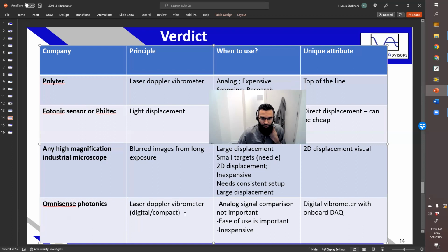For the OmniSense Photonics, it's kind of a unique device. It combines a lot of the attributes from all of these. I like the fact that it's inexpensive, and also you can have a standoff distance, and you don't need an oscilloscope, which can be a plus and a minus. You might want to put it into an oscilloscope, but you also might not want to if you just want a simple test that an assembly worker does at the end, or if you want another way to verify your transducer is working, and it's not important to you to put all those waveforms together.